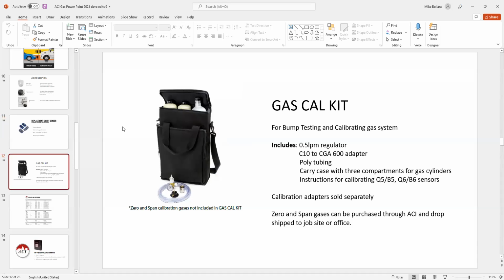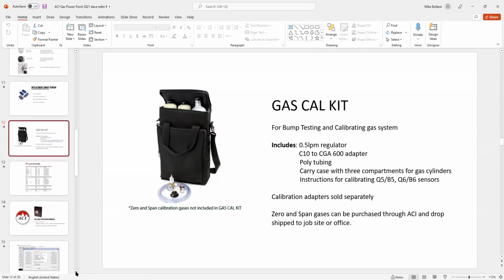So we do offer a gas calibration kit. This is one of the big questions we get asked: do we handle the calibration gas? And yes, we do. So we put this gas cal kit together. It includes the 0.5 liters per minute regulator, the adapter that goes from C10 to CGA 600, the poly tubing, and the carry case. The calibration adapter that goes on the front of this Q5 or Q6 is sold separately, because this kit can be used with our Q8s, which is explosion proof and requires a different type of adapter. Like I said, the zero gas and the span gases can be purchased through us. That is on the data sheet. We'll have a drop ship directly to either your job site or your office. It makes it a lot more convenient to order everything on one PO, and it comes at one time.